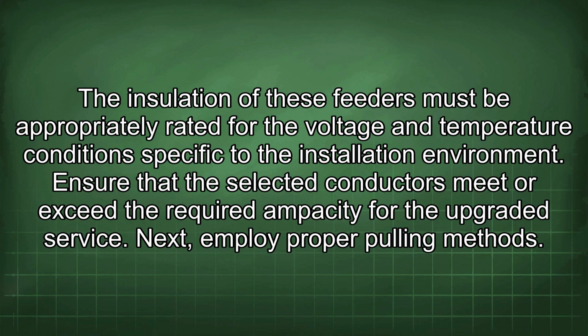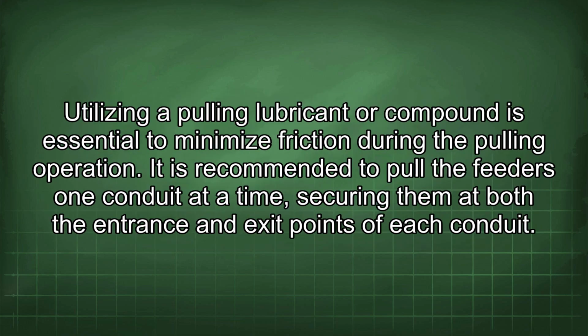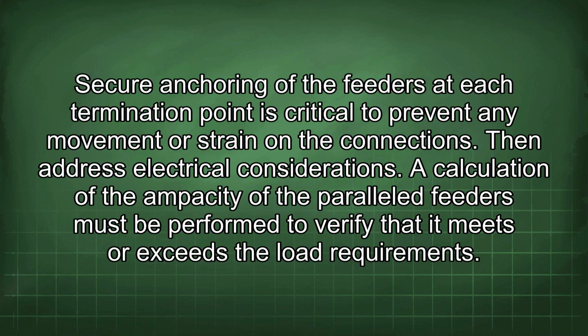Next, employ proper pulling methods. Utilizing a pulling lubricant or compound is essential to minimize friction during the pulling operation. It is recommended to pull the feeders one conduit at a time, securing them at both the entrance and exit points of each conduit. Secure anchoring of the feeders at each termination point is critical to prevent any movement or strain on the connections. Then address electrical considerations.